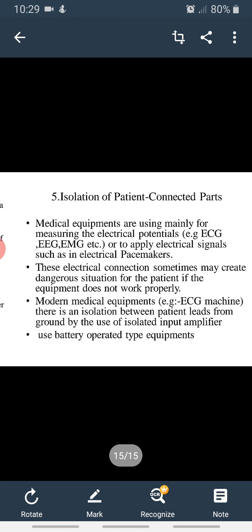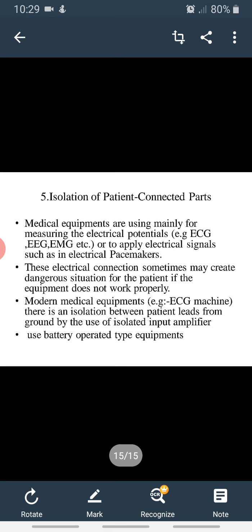And fifth one, isolation of patient connected parts. Medical equipments are mainly used for measuring electrical potentials like ECG, EMG, EEG, etc. or to apply electrical signals such as in electrical pacemakers. These electrical connections sometimes may create a dangerous situation for the patient if the equipment does not work properly. In modern medical equipments like ECG machines, there is an isolation between the patient's leads and ground by the use of an isolated input amplifier, or battery operated type equipments are used.